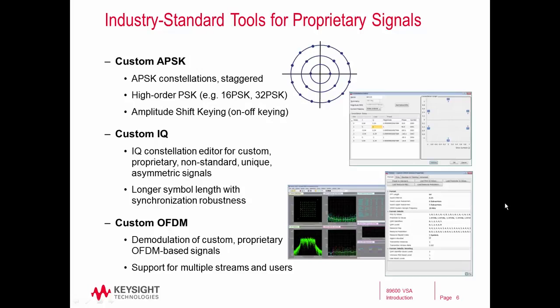In all of these cases, you're able to define your signal constellation and then in the VSA software get results for constellation diagram and error vector magnitude. You're able to look at your EVM versus symbol or versus subcarrier for OFDM signals. So a lot of results and flexibility are provided for these custom signals.